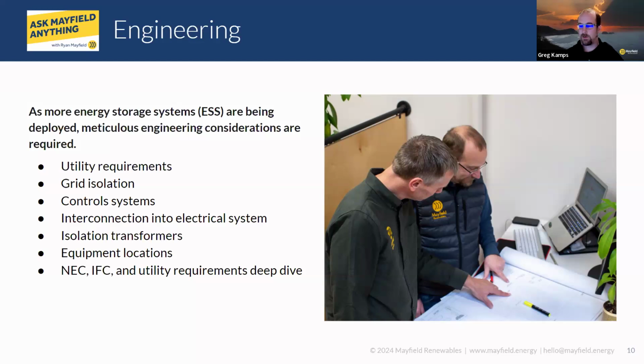Typically what we've been using a lot of is grid isolation, either a contactor or a motorized breaker or something like that, that when the grid goes away, it isolates and cuts off the grid so that there's no interaction anymore. That's one of the things the utility cares a lot about - they want to make sure that what you're proposing to use satisfies their requirements. A lot of what we're using is like an SEL relay with an appropriately sized contactor or a motorized breaker. There's a few different reasons to use one over the other, but it relates to the existing equipment, how everything's going to be interconnected to that equipment, what the goals are, what the backup goals are. There's a lot into it, but those are a couple different ways to do the grid isolation.